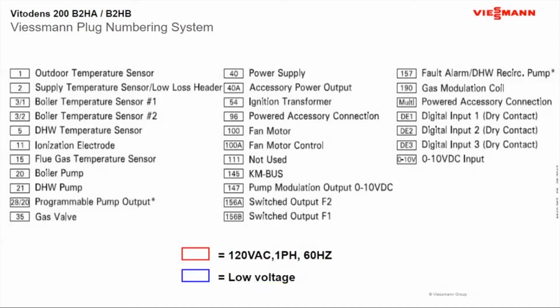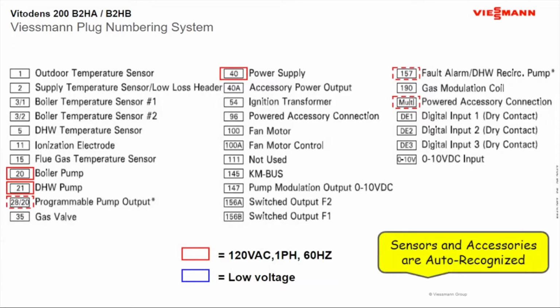Here's our plug numbering system. So you'll see in the red, mostly all our line voltage outputs or inputs. And then in the blue, you'll see mostly all our low voltage or sensors. Remember, the sensors are auto recognized. So as soon as you attach it to the boiler, it now knows it has that. So our outdoor sensor, 2 sensor or 5 sensor, once you plug those in, it knows it has something connected to it. You do have to have the outdoor sensor connected to the boiler, whether you use it or not. You have to have it tied into this boiler, whether you put it outside or not. It still has to be connected.